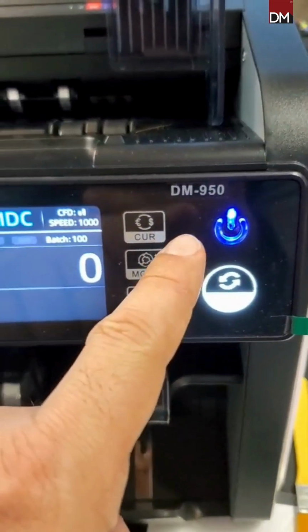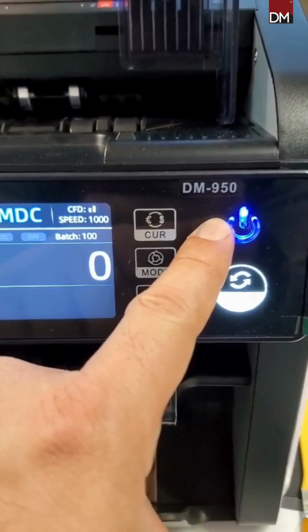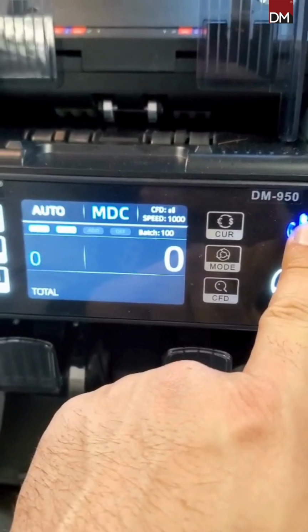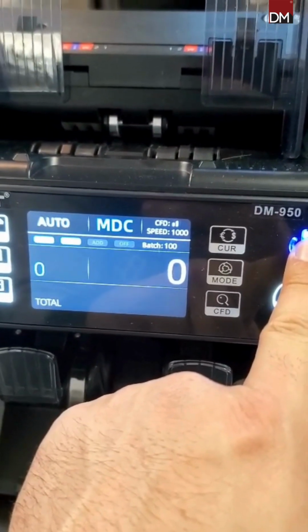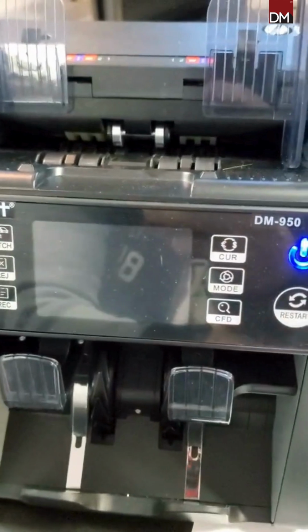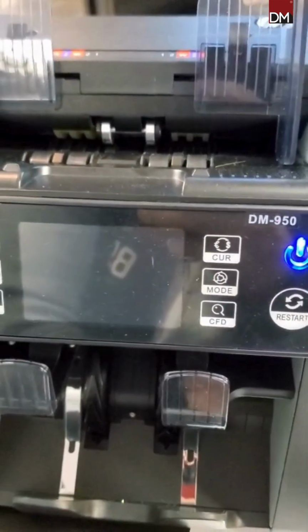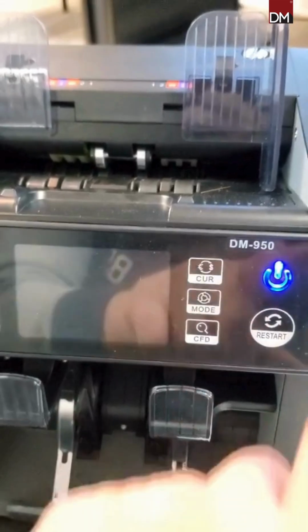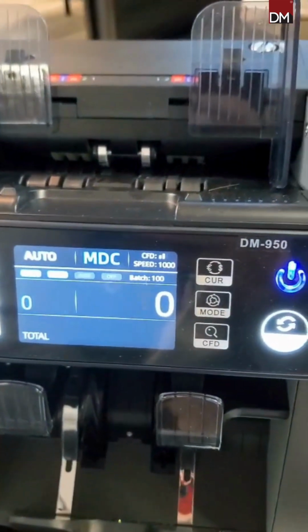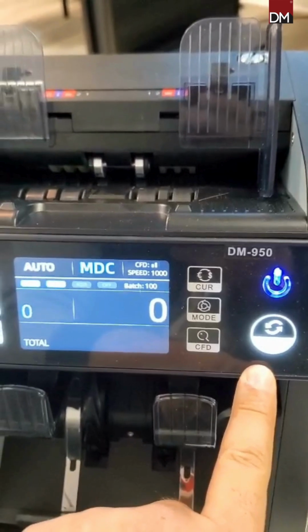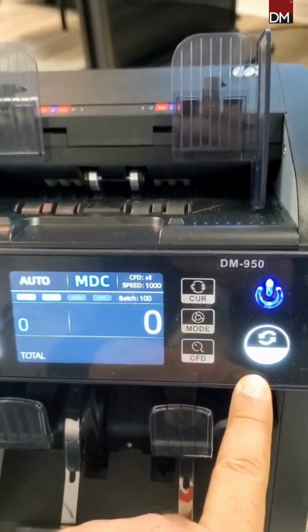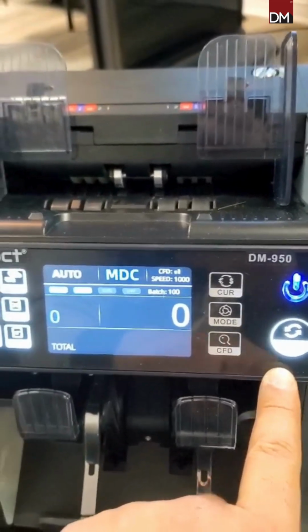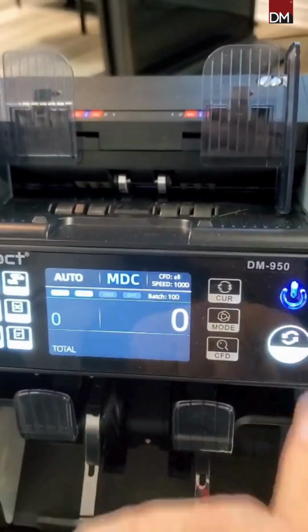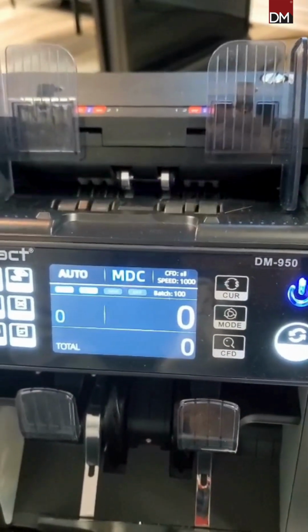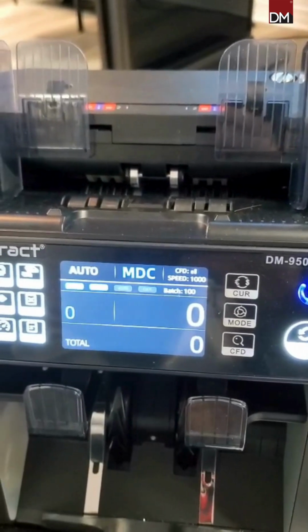And of course we have over here our power key, where if you press it for long, let's say about 5 seconds, and then you release, the machine will be on standby. We always recommend you do this by the end of the day, and also you press it again if you want to resume. Also the restart key over here to start counting or other operations, and it will also clear the counting result over here. So just give it a little press and it just resets everything so you can recount again.